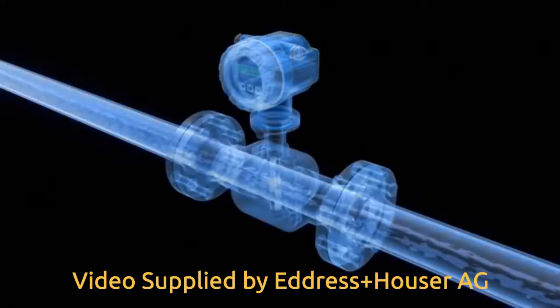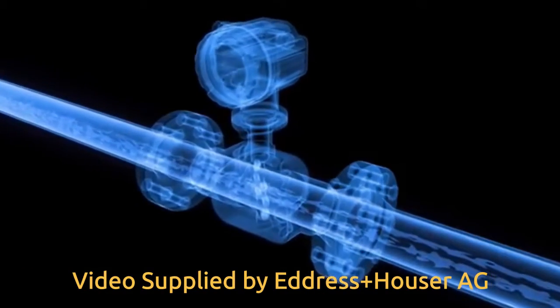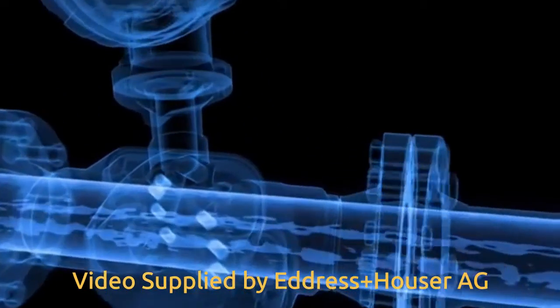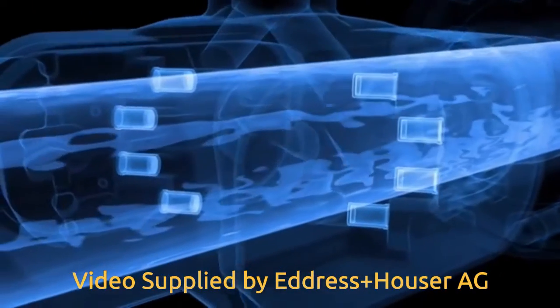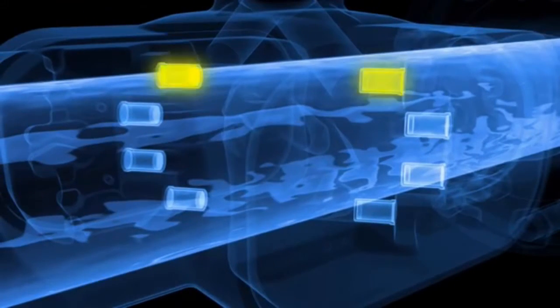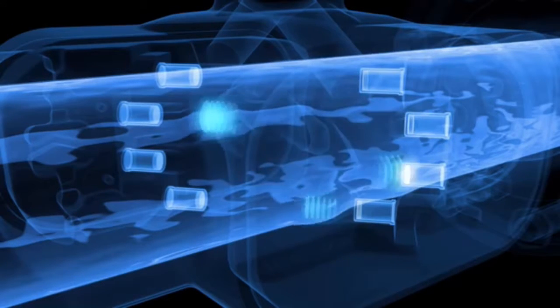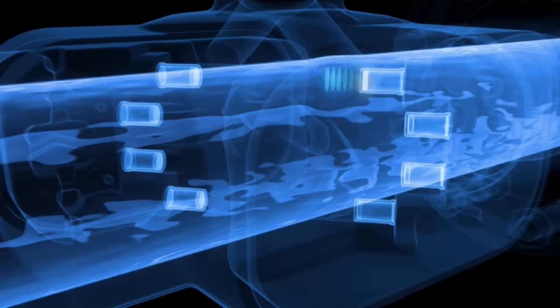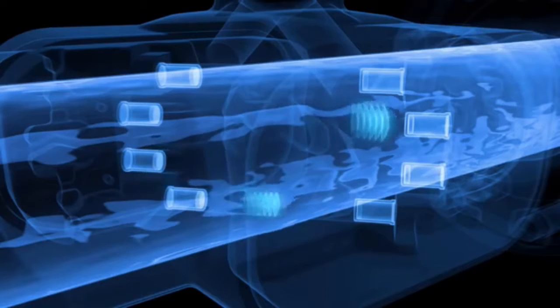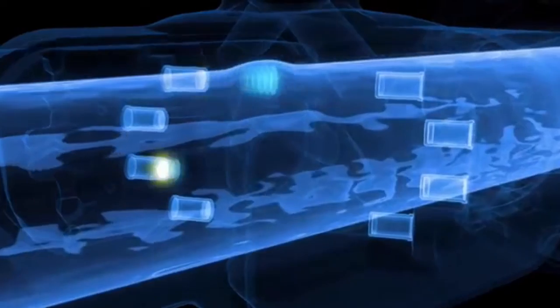Inside the ultrasonic flow meter, pairs of sensors are fitted across from each other in the measuring tube. Each sensor can alternate between sending and receiving an ultrasonic signal. The times between these signals are measured. The ultrasonic signals are generated by electronic crystals that apply a voltage and create voltage when they are impacted by an ultrasonic signal.